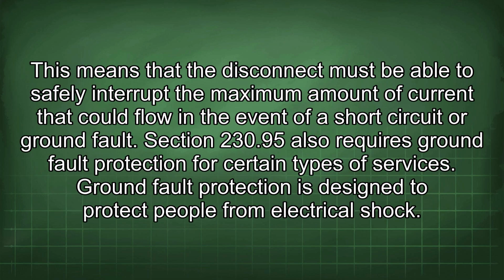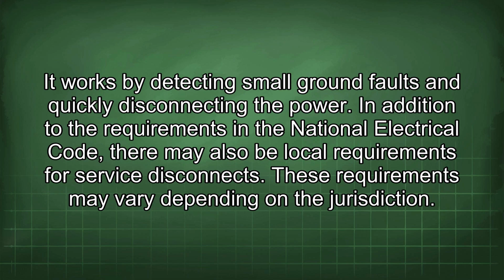This means that the disconnect must be able to safely interrupt the maximum amount of current that could flow in the event of a short circuit or ground fault. Section 230.95 also requires ground fault protection for certain types of services. Ground fault protection is designed to protect people from electrical shock. It works by detecting small ground faults and quickly disconnecting the power.